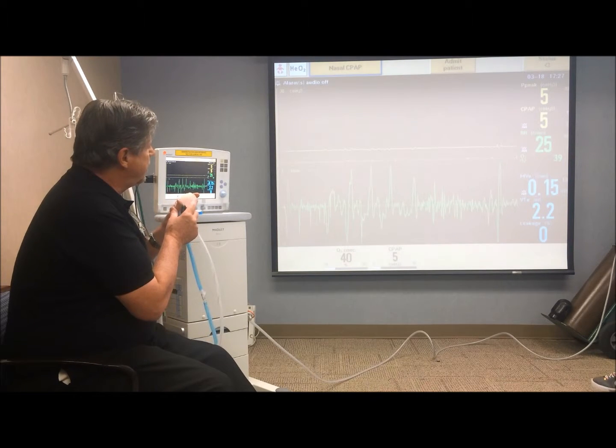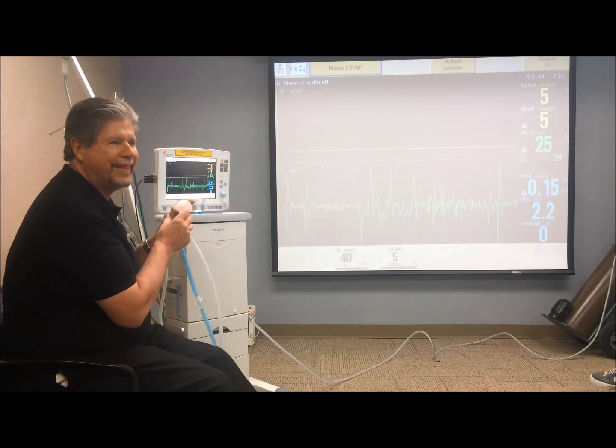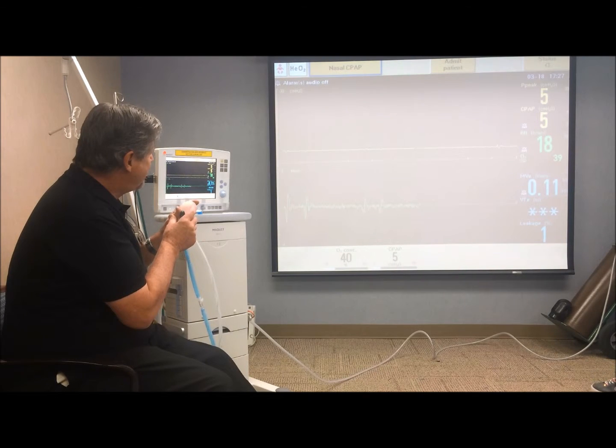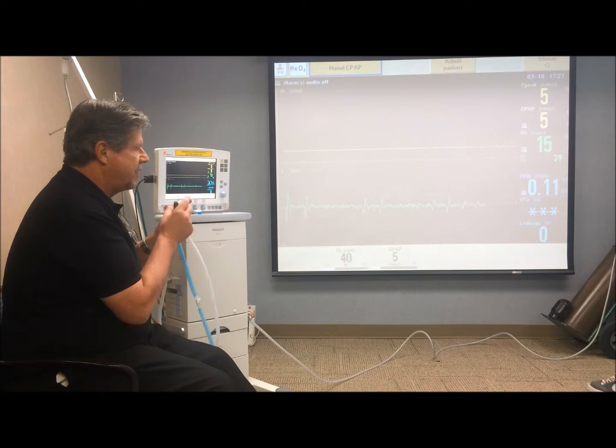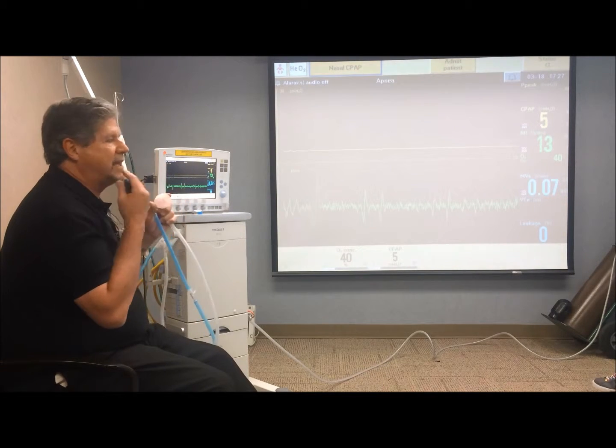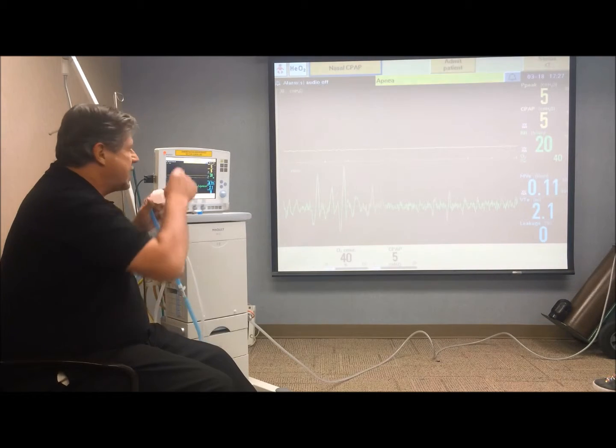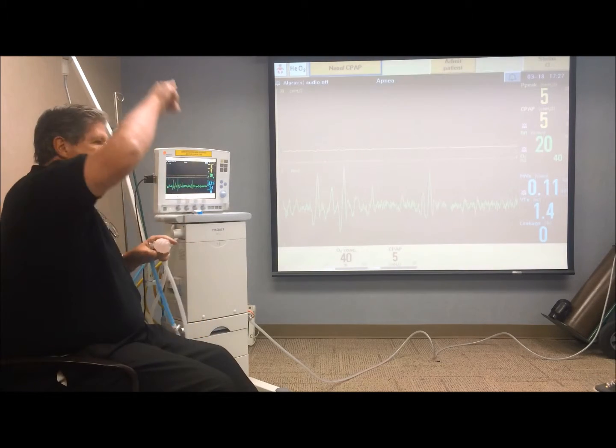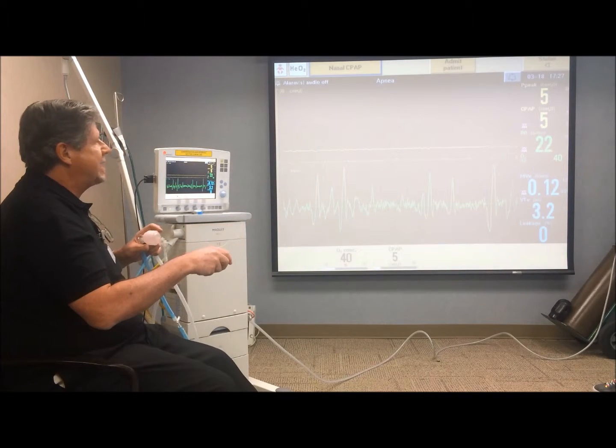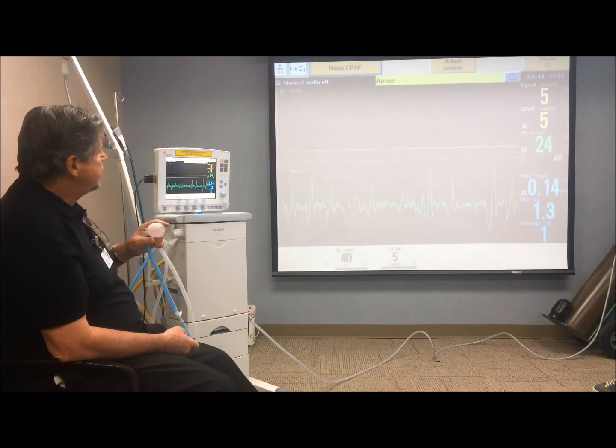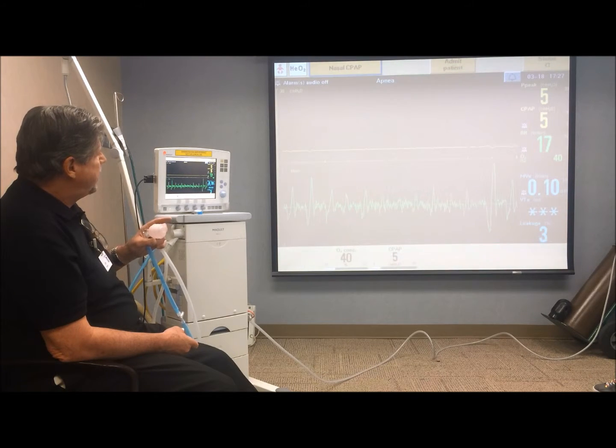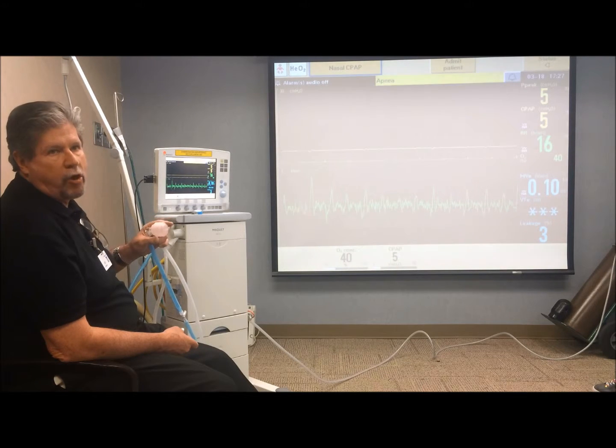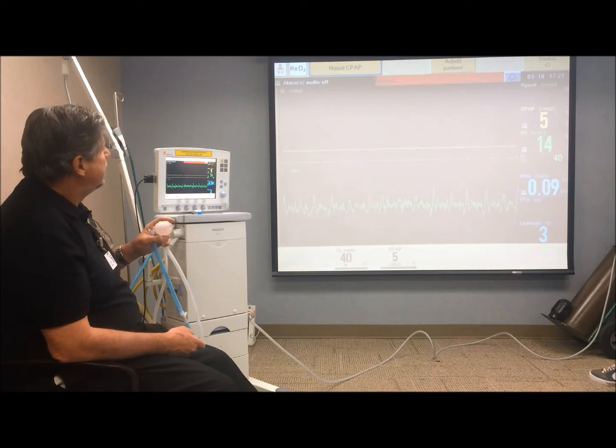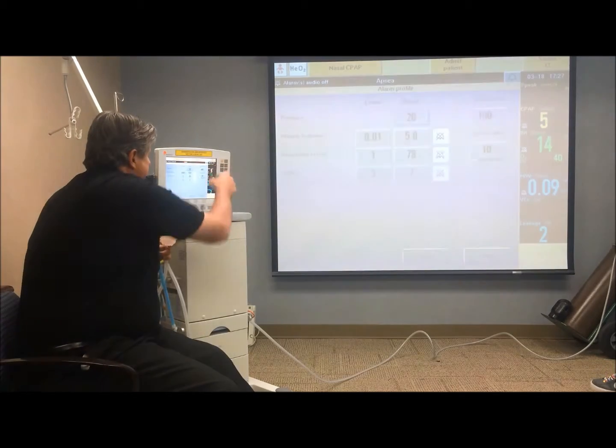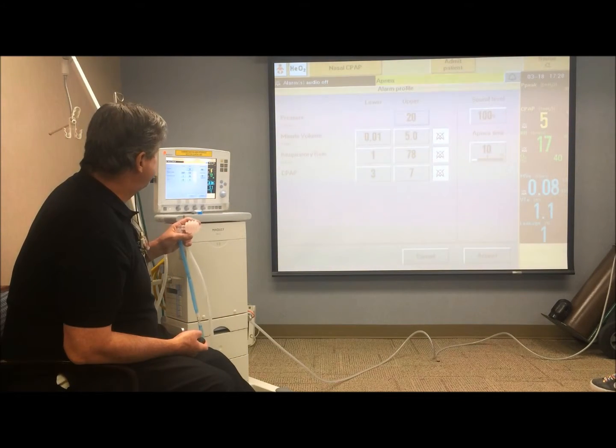So what happens is, sometimes the leak is enough, so the baby is still breathing, still getting the benefit of pressure, but because there isn't enough deflection of the upper flow to the bottom flow, it can't count the rate. So sometimes we'll see, even though the baby's breathing, the ventilator will give us an apnea alarm, because it's apnea now, and it can't count that rate.